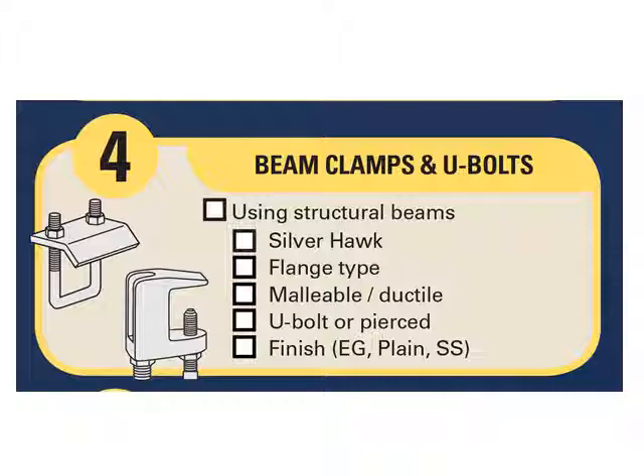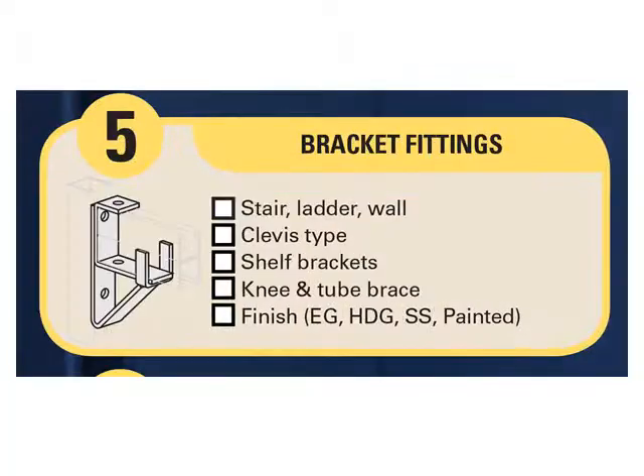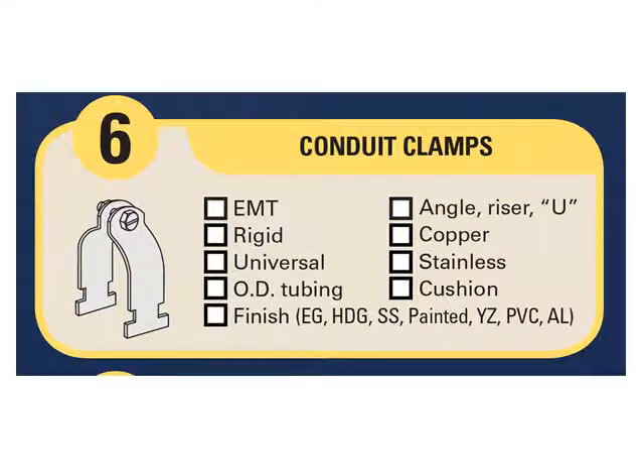Number four: beam clamps and U-bolts — fastens the channel to structural beams and supports. Number five: bracket fittings — fastens the channel to vertical planes, typically to create shelves for equipment or general storage. Number six: conduit clamps. Securing conduit and pipe overhead is perhaps the most common application for a strut system. Special clamps are available for the full spectrum of pipe and tube, from the very lightest conduit to the heaviest black pipe. These include EMT, rigid, universal, OD tubing, riser, copper, stainless, cushion, and U-clamps.